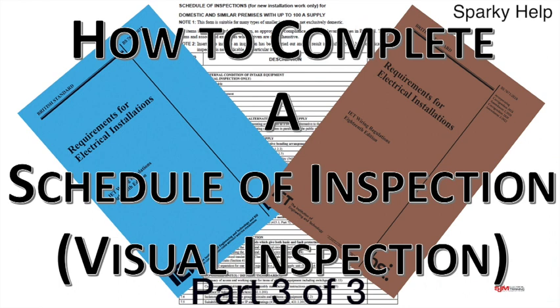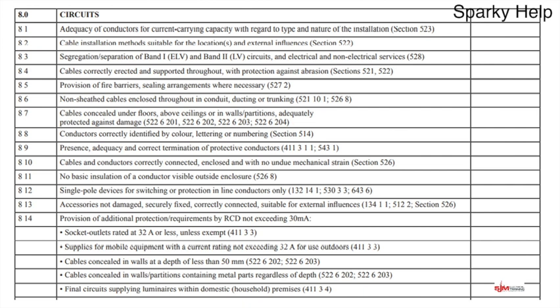Let's continue with circuits. Adequacy of conductors for current carrying capacity — this links to the previous one where the breaker or conductor was wrong. It could be the breaker was right but the cable was wrong, so without further investigation you're left in limbo. You're making sure it meets the requirements as installed, including checking that for an 8 kilowatt shower you have an appropriately sized cable, and hopefully the designer has done that so you're checking against the design information.